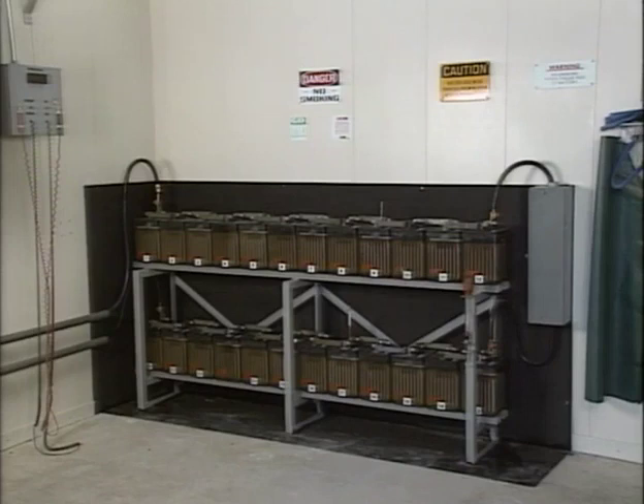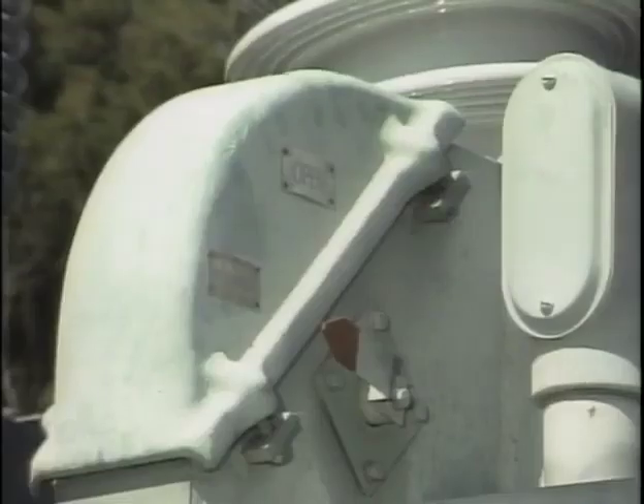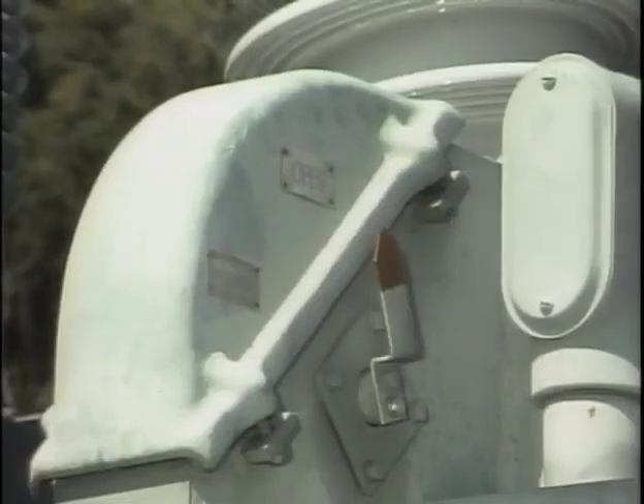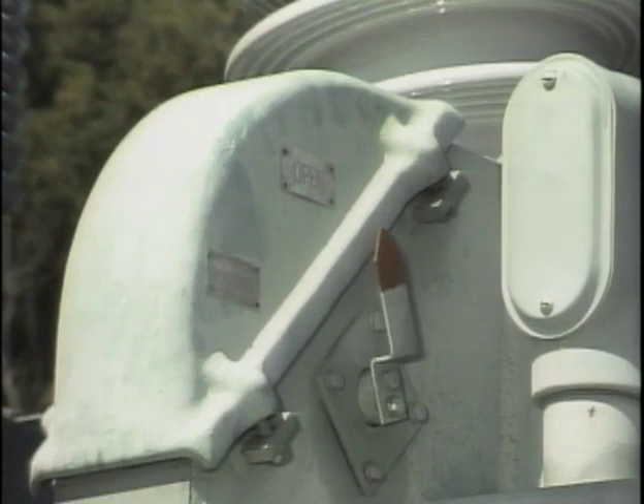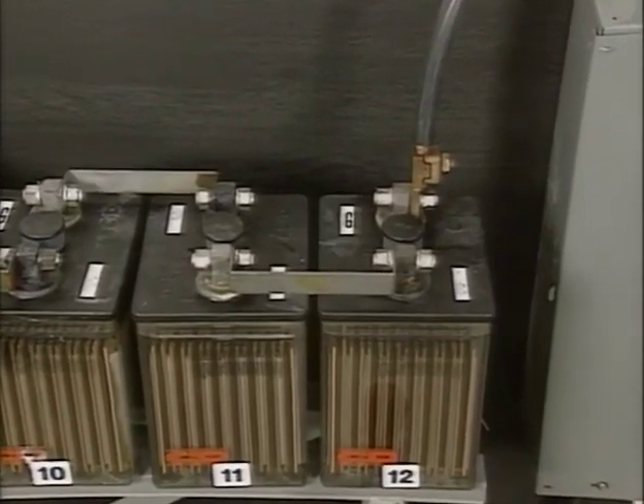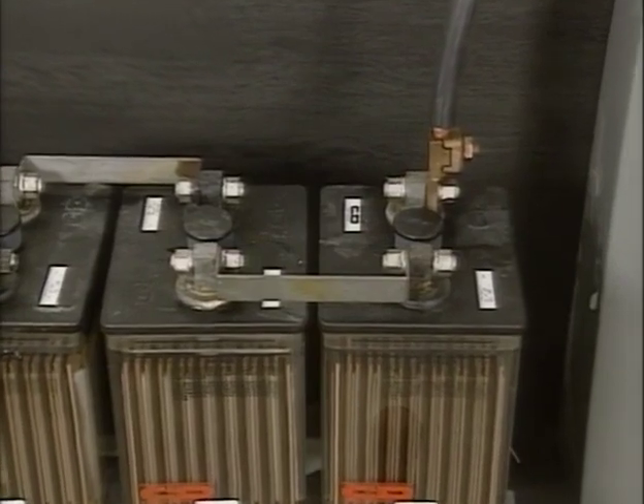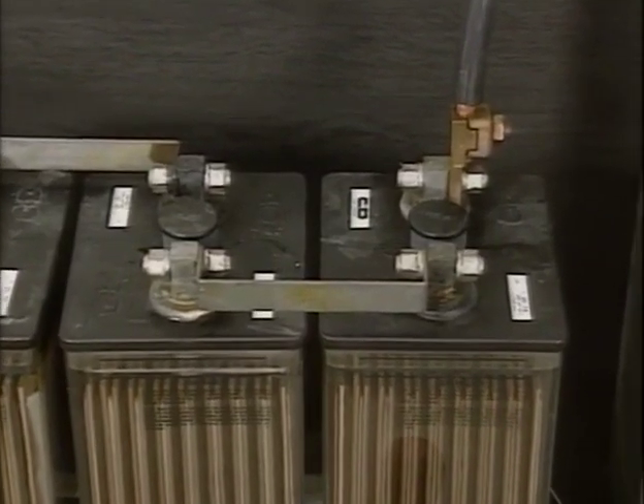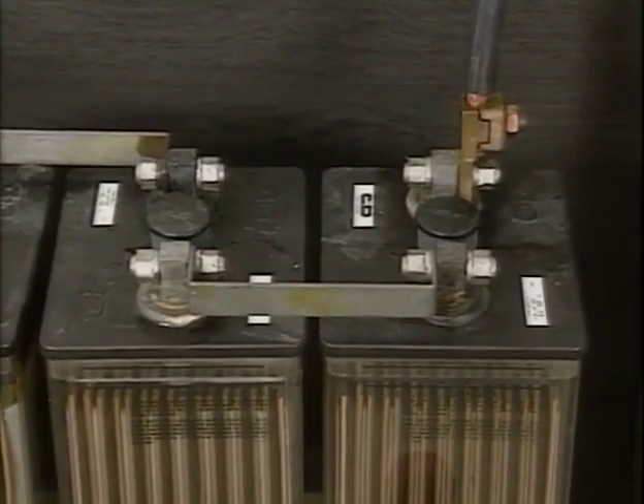Typically, when a substation battery is needed, it must deliver a high momentary current to trip circuit breakers. It's during high discharge currents that problems occur in the battery's connections and intercell conductors. In fact, a large percentage of battery system failures are due to defects in internal connections, terminal post connections, the intercell connectors, and jumpers. These defects show up as higher than normal voltage drops during an integrity test.